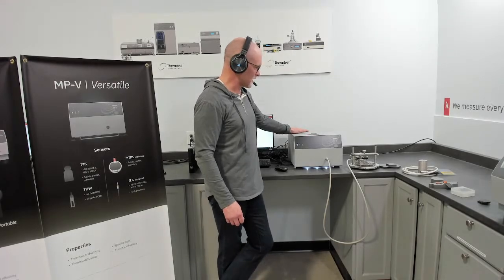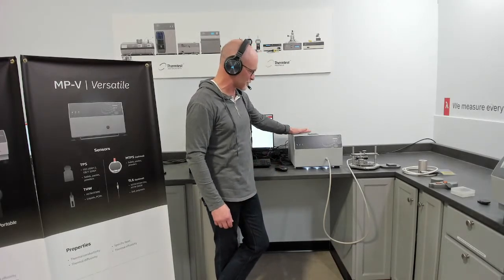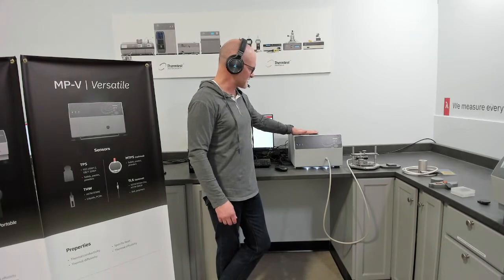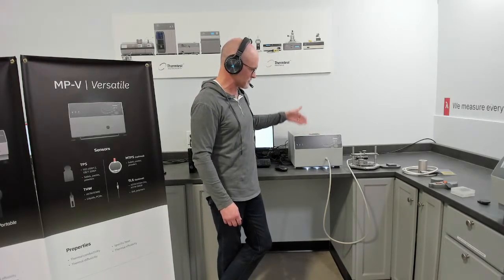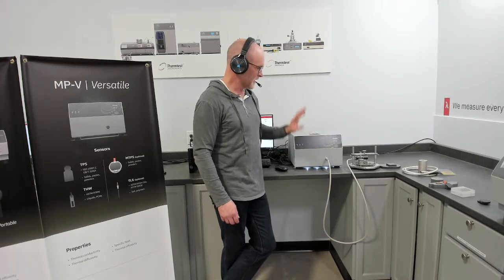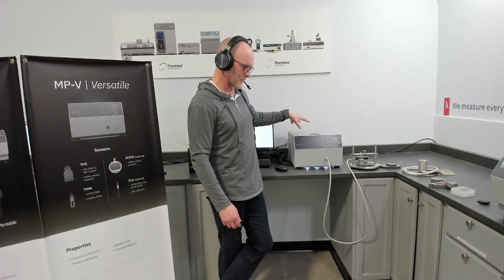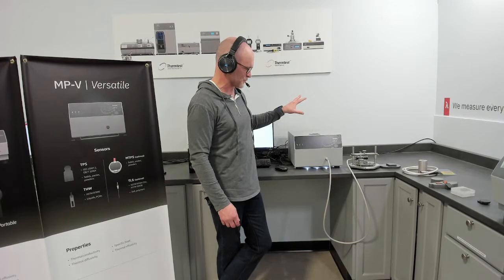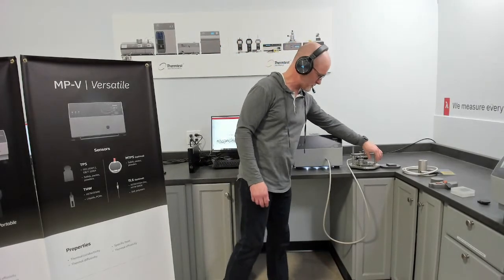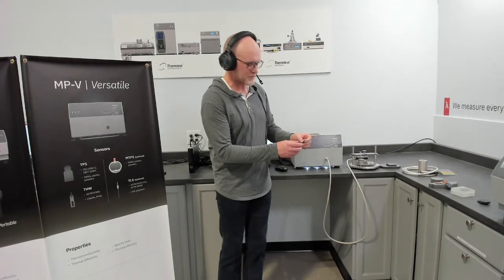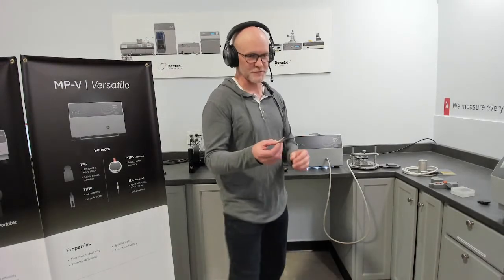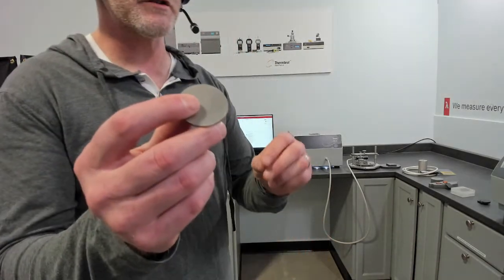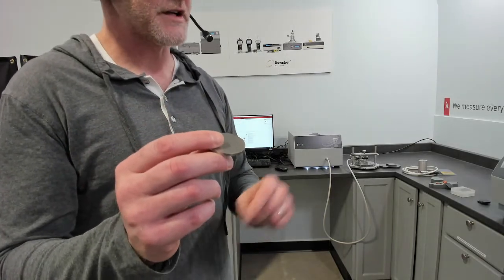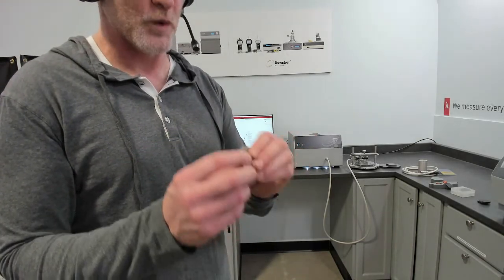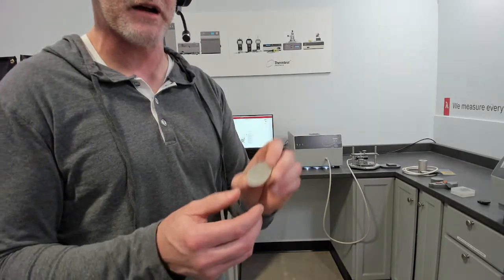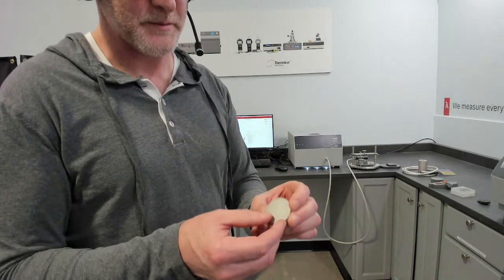So again, for solids, pastes, and powders following transient plane source in the ISO, the basic package comes with 3 transient plane source diameters, as shown here. In addition to the bulk method for measuring bulk thermophysical properties, we've included the slab module, which allows you to measure symmetrically conductive sheets. This is for materials that are thin in nature, in the range of 0.1 to 100 watts per meter Kelvin, or 500 watts per meter Kelvin depending on if you have the max power package.